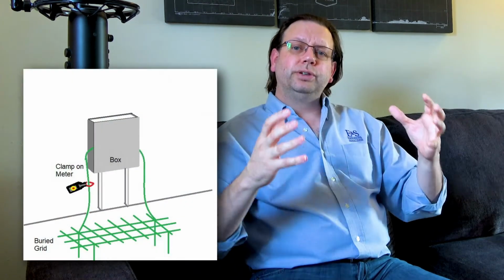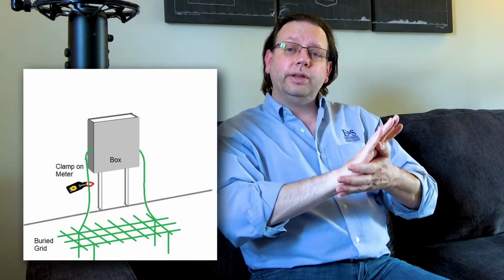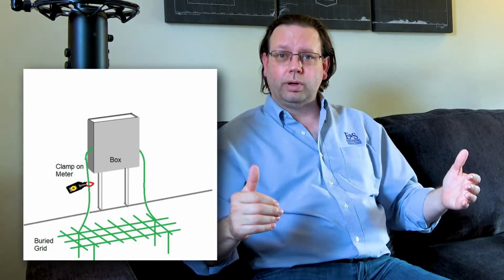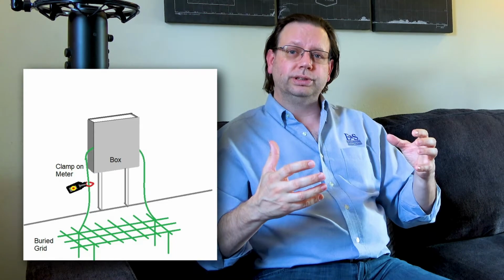We're in our substation. We have, say, a switch, and there's 2 ground wires tied to it. It's a big square box with stuff in it, right? And that square box outside is covered with a metal case, and it's got 2 ground wires bonded to it, leading down to our grid to make sure that any charges that got on that case had a path to ground, right, and balances the voltages.